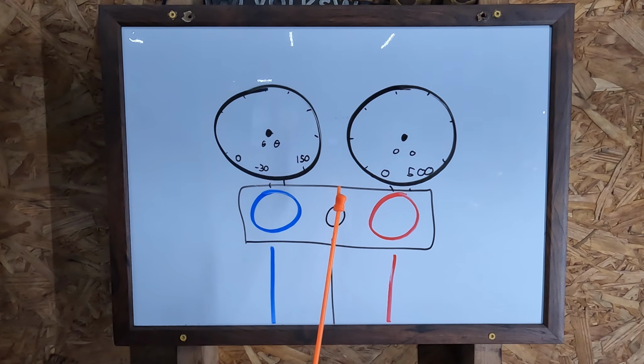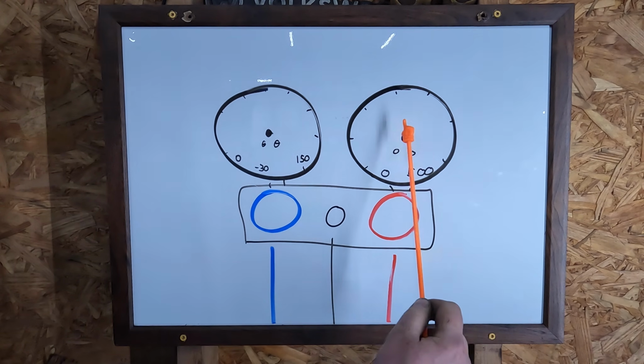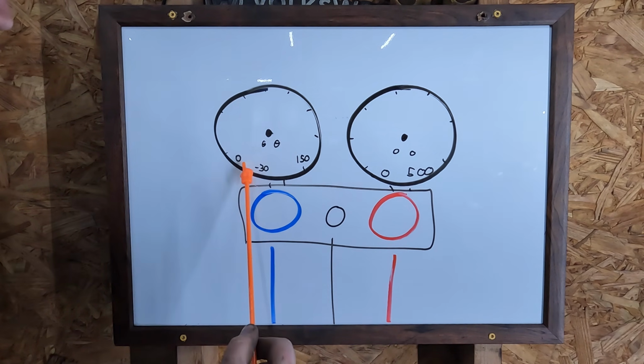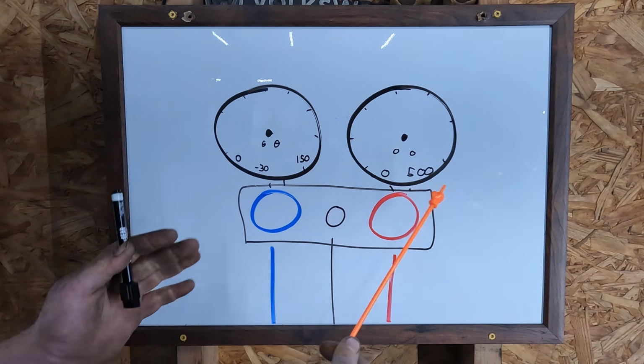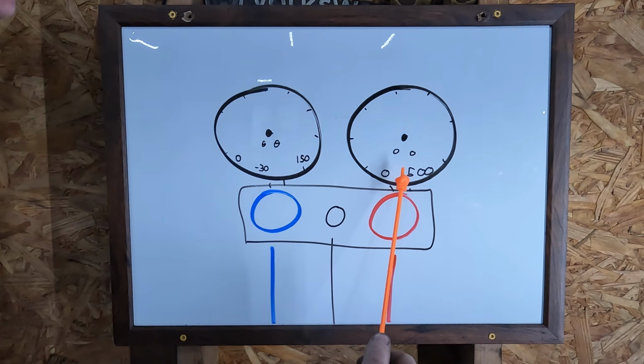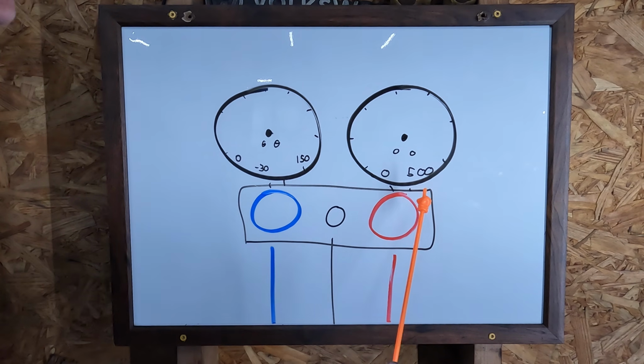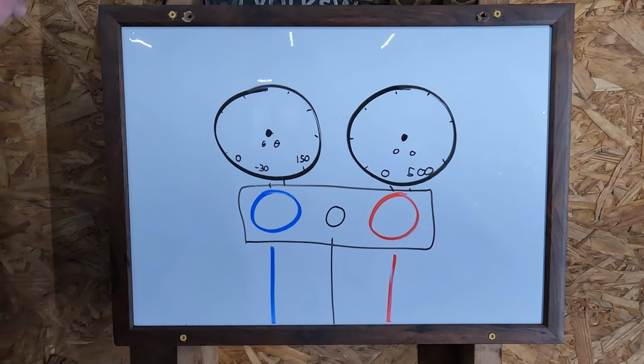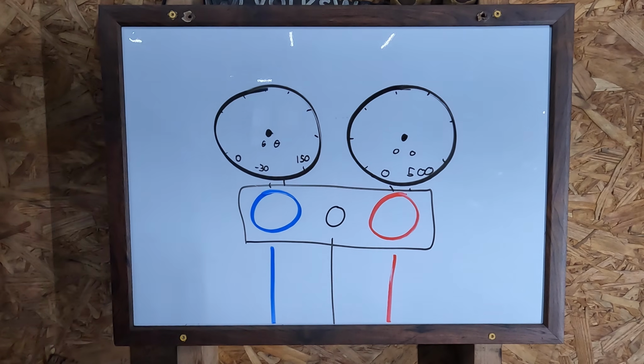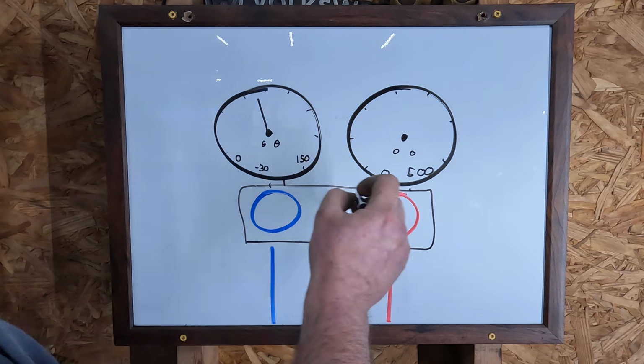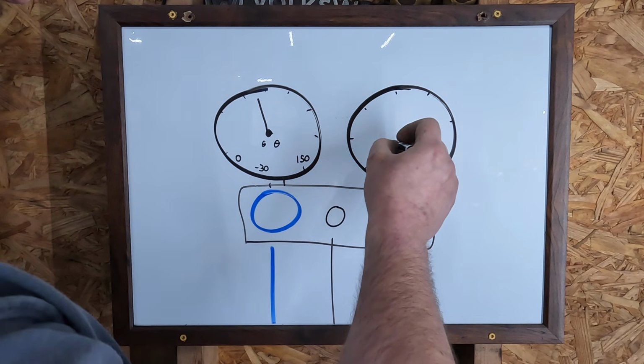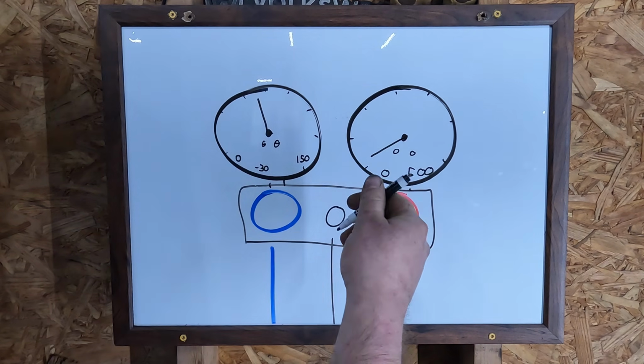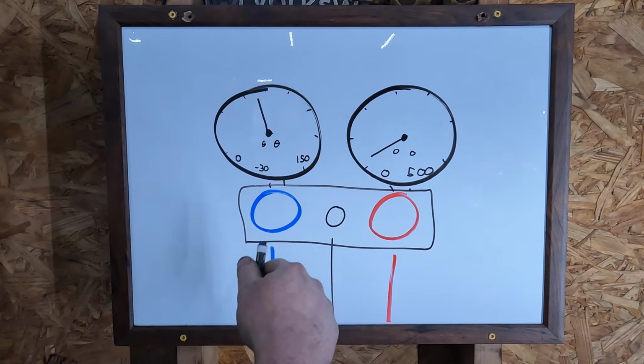So an important thing to keep in mind is the scale of these two gauges is completely different. Your low side gauge is going to have a vacuum range and then a normal range up to somewhere around 150, but your high side gauge is going to go from 0 up to maybe around 500. So at rest, if you have that supposed 70-ish PSI, your gauges are going to look something like that. And that's showing an equal 70 PSI on both sides.